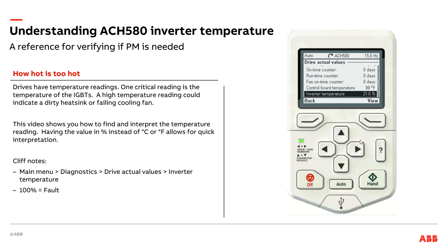We found out that with previous generation drives, when we talked about the inverter temperature — the IGBTs in degrees Celsius or degrees Fahrenheit — we got a lot of concerned folks saying, 'Oh, this is at 60 degrees C or 90 degrees C, there's got to be a problem.' But these devices are actually designed to run at those temperatures without a problem. So what we wanted to do is take the temperature concept and convert it into something meaningful and easy to understand. We decided to go with percentage.